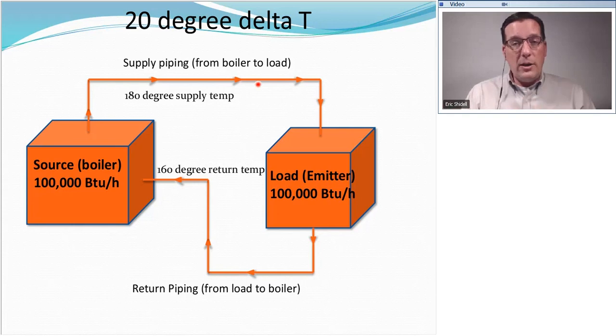What we'll experience when we do that, and you'll find this everywhere you go, you're going to find lots of systems that have too high of a flow rate. If you damper that down a little bit and get to that 20 degree difference, instead of say a 5 or 10 degree difference, suddenly the home is more comfortable. The heating bills go down, because that whole time we were rushing that water through that boiler and not picking up heat, we're still running the burner, and that heat was going right up the chimney to heat the birds.